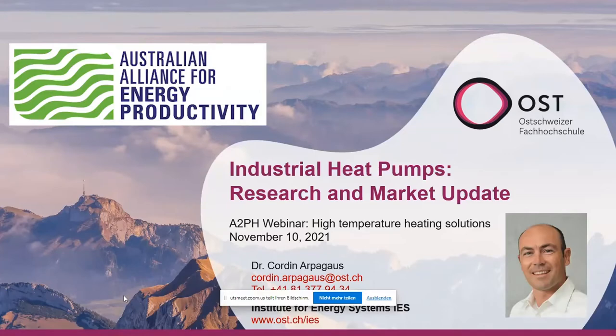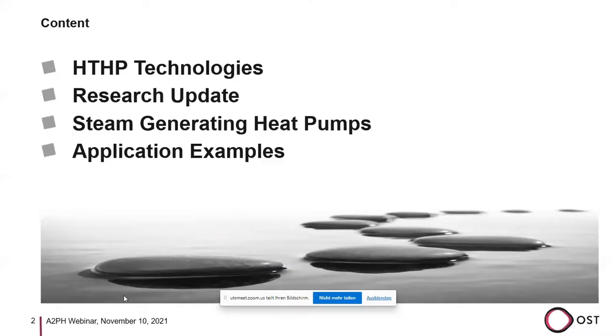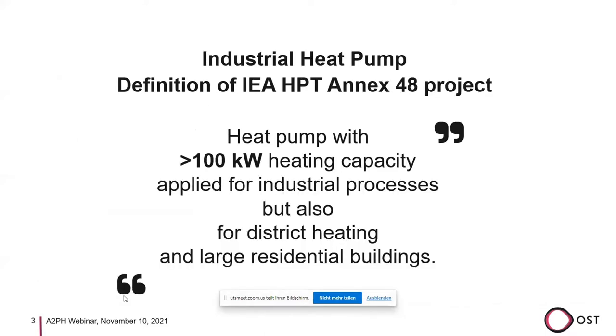So I'd like to give you an update on research and market on industrial heat pumps. I speak about technologies, give a research update, go into steam generating heat pumps especially, and look at different cycles, and then also application examples and case studies. So first of all, what is an industrial heat pump? It's a definition from Annex 48. We say it's 100 kilowatts and higher heating capacity for industrial processes, but also for heating and for domestic large residential buildings.